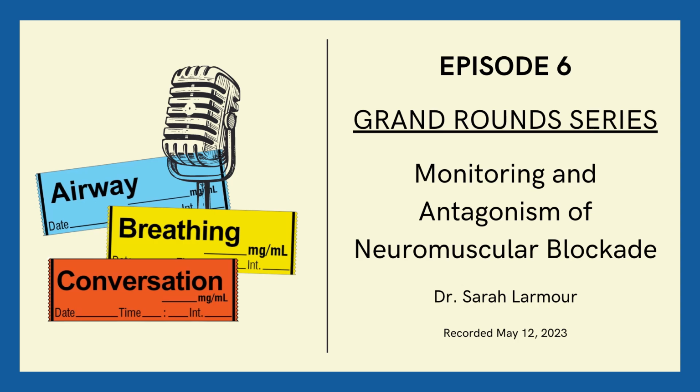EMG, or electromyography, is a measurement of the muscle action potential following nerve stimulation. So the amplitude of the signal is proportional to the number of activated muscle fibers, which is proportional to the force of contraction. Because we're measuring an electromyogram of the stimulated muscle, free muscle movement is not required. That means that we can use it in all surgical positions, even when the arms are tucked. The problem has been that EMG signal is influenced by other electronic devices in the operating room, and there were some engineering issues with noise management.